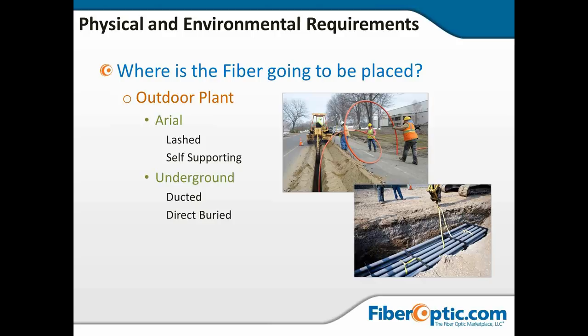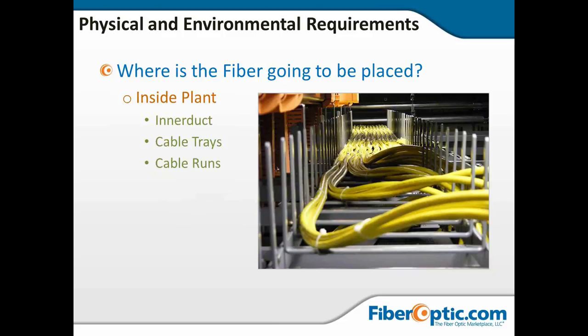For inside plant, are we going to use inner duct, cable trays, cable runs, or ladder racks? If we use duct, we need to look at fill ratios. If we use cable trays, we must consider how much fiber can fit, how many fibers to add later, and ease of removal of legacy fiber. If you pull through inner duct and want to remove old plant, you'll have more problems than with an open tray. All of these must be weighed against future needs.